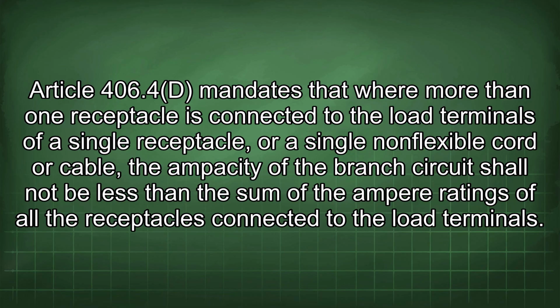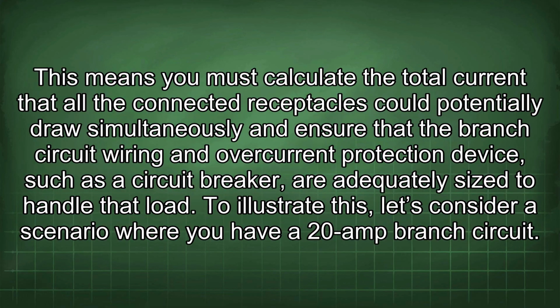Article 406.4d mandates that where more than one receptacle is connected to the load terminals of a single receptacle or a single non-flexible cord or cable, the ampacity of the branch circuit shall not be less than the sum of the ampere ratings of all the receptacles connected to the load terminals. This means you must calculate the total current that all the connected receptacles could potentially draw simultaneously and ensure that the branch circuit wiring and overcurrent protection device, such as a circuit breaker, are adequately sized to handle the load.